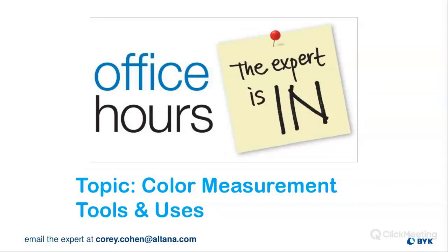Corey, you know better than I. Yeah, that tends to be an issue with these profilers because of how sensitive the measurement is. The gloss and reflectivity measurement that these things do is very sensitive to any sort of dust or scratching or anything that might be either on the standard or on the lenses. So we recommend, first of all, you never want to rub it dry, and you never want to use anything but a lint-free wipe, like a Kim wipe. And so we recommend cleaning it with some distilled water.